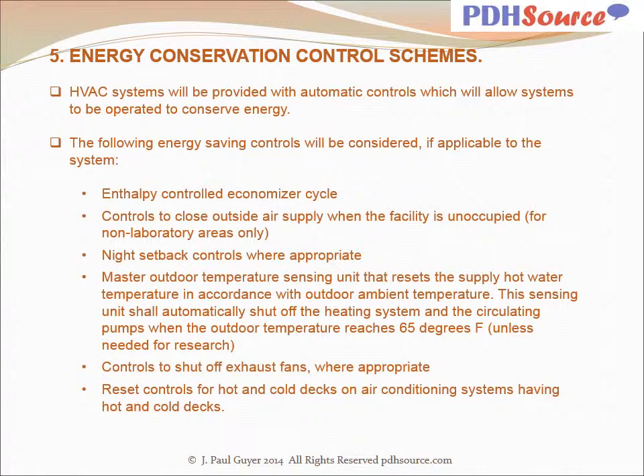Master outdoor temperature sensing unit that resets the supply hot water temperature in accordance with outdoor ambient temperature. This sensing unit shall automatically shut off the heating system and the circulating pumps when the outdoor temperature reaches 65 degrees Fahrenheit unless needed for special research purposes. Controls to shut off exhaust fans where appropriate. Reset controls for hot and cold decks on air conditioning systems having hot and cold decks.